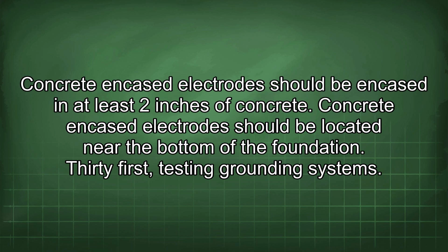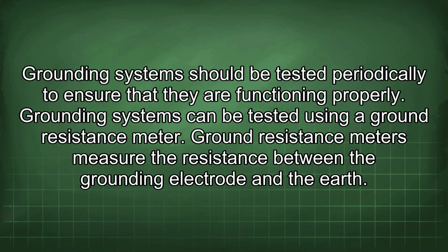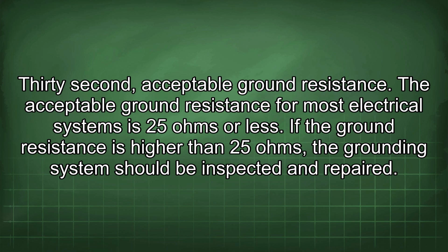31st, testing grounding systems. Grounding systems should be tested periodically to ensure that they are functioning properly. Grounding systems can be tested using a ground resistance meter. Ground resistance meters measure the resistance between the grounding electrode and the earth. 32nd, acceptable ground resistance. The acceptable ground resistance for most electrical systems is 25 ohms or less. If the ground resistance is higher than 25 ohms, the grounding system should be inspected and repaired.